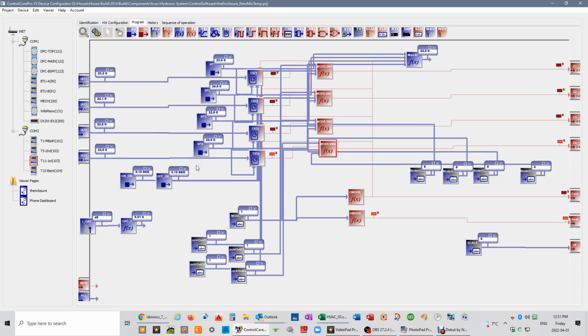I can set it to off, and none of these actuators will come on regardless of what the set point and current temperatures are. And then I've also got winter cooling, which I've just started to program, which is going to allow me to open up an actuator if the temperature in that room is significantly higher than the set point, and the overall system, so all zones, are somewhere requiring heat. What that will do is allow the room's water to circulate, extract that energy, and take it back to the buffer tank to use for the zone that is below the set point somewhere else in the house. And that will restrict the need of the heat pump to run.